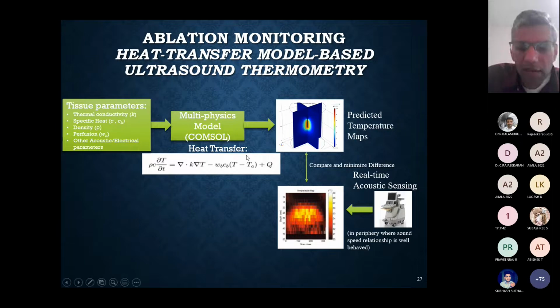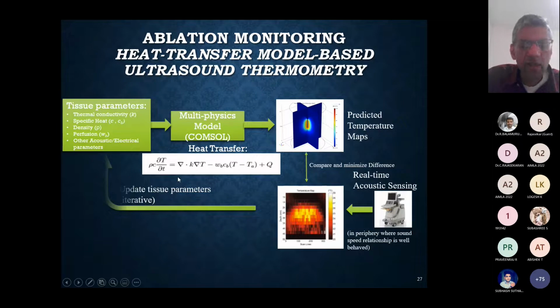This is what we try to optimize in an iterative manner using this algorithm. We do the forward simulation, compare the result with what we measured using the ultrasound transducer, look at the difference, and use it to optimize the tissue parameters. This is where the iterative step comes in — continuously optimizing the in situ tissue parameters so that the predicted temperature rise from the model matches the ultrasound measurement. It becomes an iterative minimization approach, trying to find the optimal set of tissue parameters such that this difference is minimized.